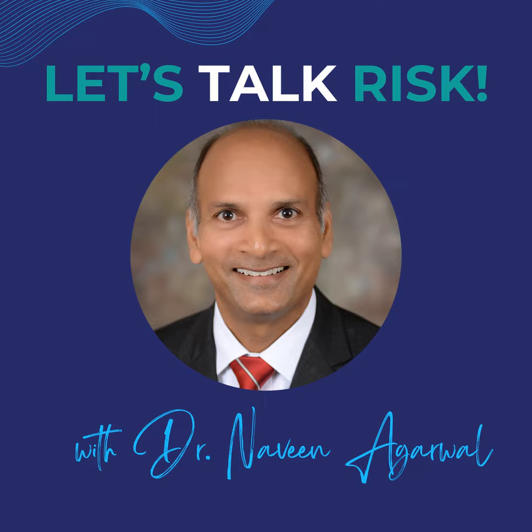Yeah, what I've tried to do in situations I've been in is even advocate for doing risk assessment pre-design controls, like in the concept phase. And that's trying to bring in things from like 14971, things like the technical report, into that phase. But it's been a challenge on the technical side.